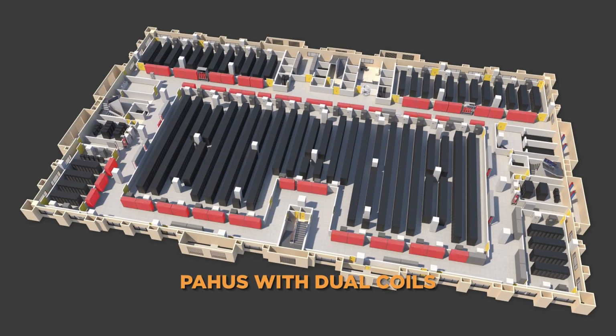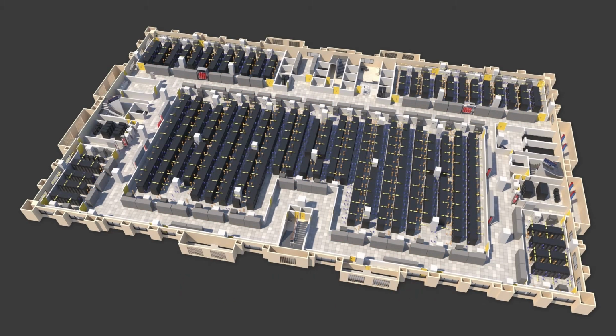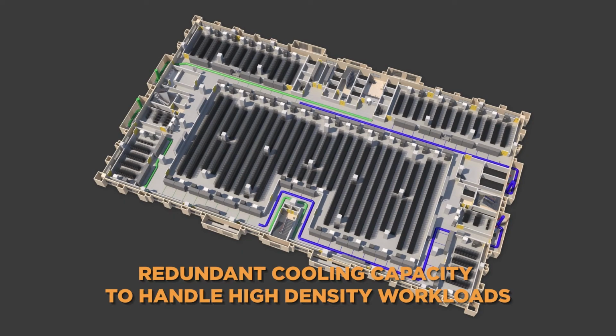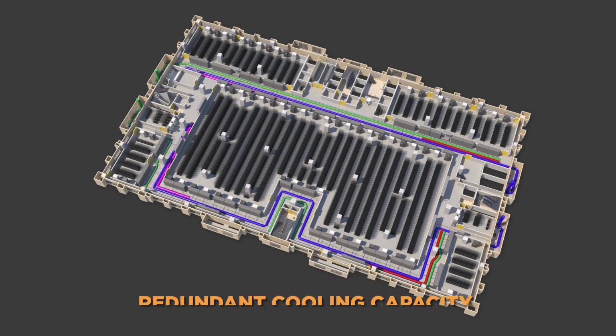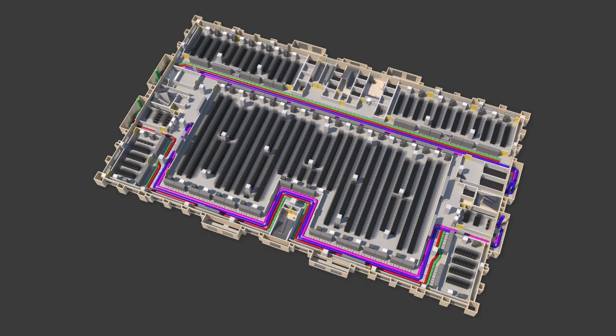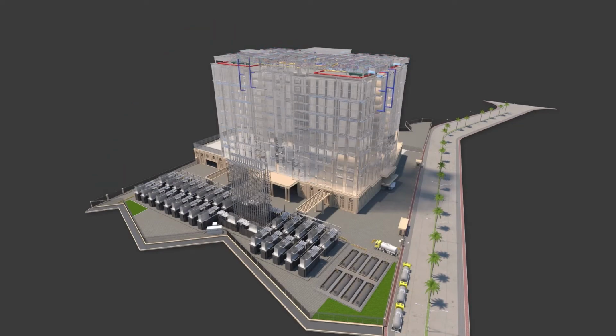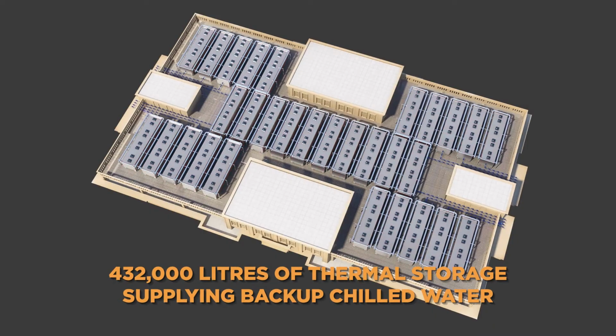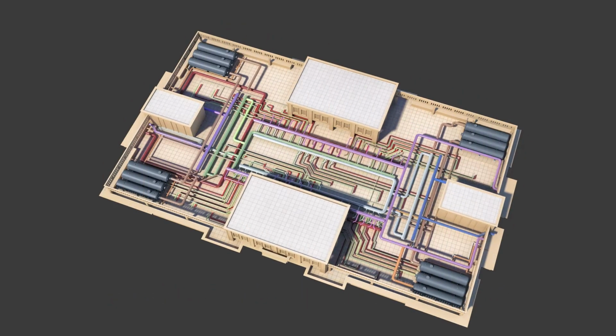Precision air handling units with redundant coils and UPS-powered fans maintain precise cooling and humidity in the server halls. Redundant coils of precision air handling units get chilled water through N plus N redundant supply lines and dispose of the hot water through N plus N return lines. 34 chillers of 400-ton capacity each supply chilled water to the precision air handling units via dual supply and return header system. In case of a temporary chiller outage, due to changeover in power source from the main feeder to diesel generator, and vice versa, the thermal storage tanks continue to supply chilled water through UPS-powered pumps to the precision air handling units, thus ensuring uninterrupted cooling to server halls at all times.